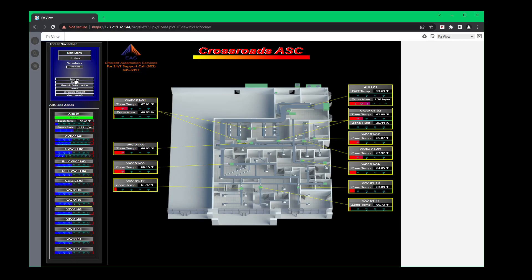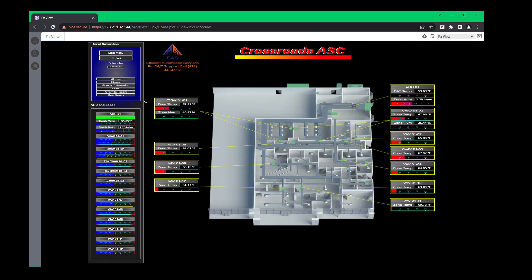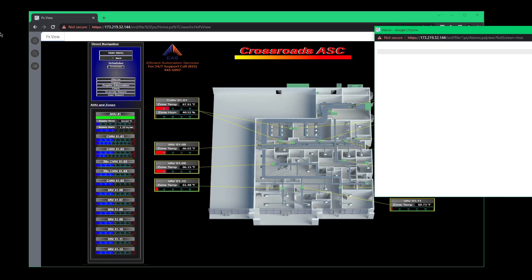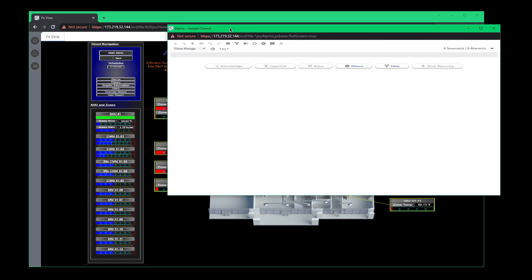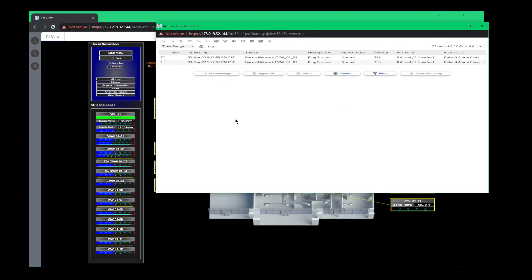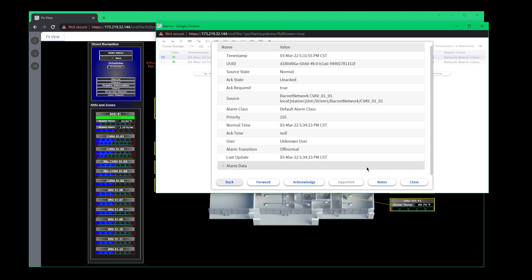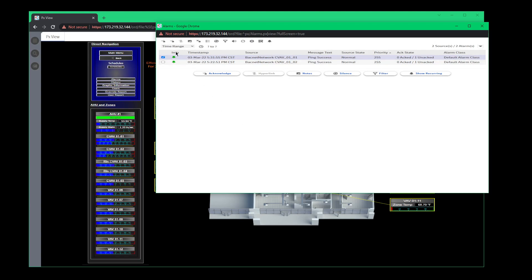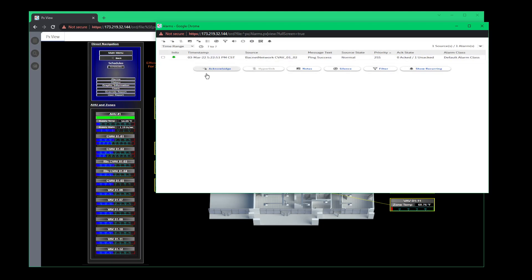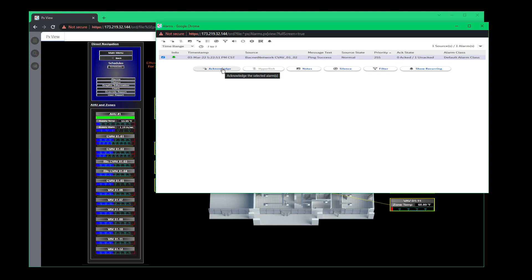So let's say for instance you want to check your alarms to see what's going on. You would click on alarm and then right now we have none or well we have these two boxes must have went offline at one point. So you can actually double click on it and it will give you all the information on the box on what was going on with that alarm. If it's in red that means it's an alarm, if it's green means that everything's returned back to normal. If you click on acknowledge after you've clicked on that it should go away. If it doesn't go away because it's red and you click acknowledge, this bell will turn gray meaning that you've acknowledged the fact that something is an alarm. But it's still there and until the alarm is cleared it'll just stay there.